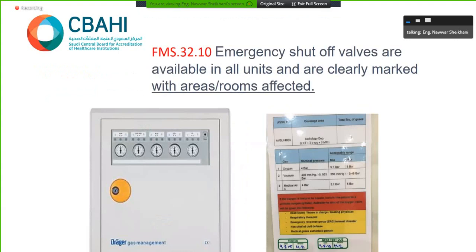32.10, emergency shut-off of valves should be available, marked with the area and room affected. As you see here, we have added a tag on the area valve service unit, mentioning the coverage area. For instance, in this slide, this AFCU covers the radiology department, the CT scan, the X-ray, whatever, okay?